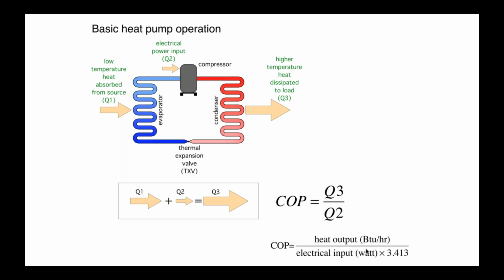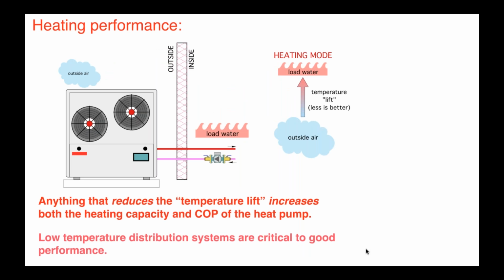We could define other COPs. One that I will talk about in part 2 is called a seasonal average COP. That's sort of like the equivalent of an AFUE rating on a boiler. But to get that, you really have to mix a lot of information together. What are the ranges of outdoor temperature? What are the ranges of water temperature the heat pump's working with, and so forth. And again, that'll be in part 2. Now, the easiest way to remember what affects heating performance is to look at what I call temperature lift.